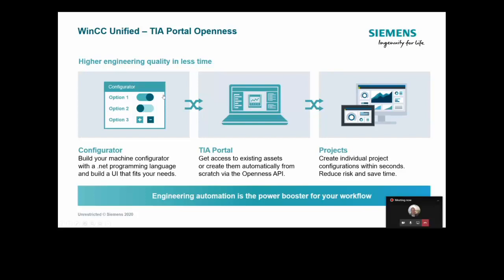A custom configuration tool can be created in .NET or whatever programming language you're comfortable with. This could be used to create an initial project — you might want to import some customer data and use it within a configuration tool to start generating a custom TIA Portal project. We can open TIA Portal, create the project, configure the hardware, add the objects, and now we've got the ability to work with the visualization systems as well — the HMI and SCADA systems. This capability didn't exist with WinCC V7 or WinCC Professional. Now we can start mass editing projects, and OEMs are building custom configuration tools for their base projects.